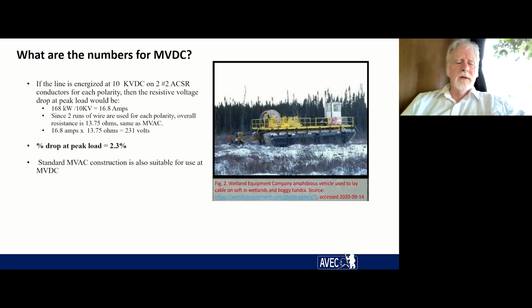This is straight Ohm's law. This is just DC current going through a resistance causing some heat that you lose. So I did that calculation at just 10 kV DC, and it's only 2.3%. So almost comparable, apples to apples, even though the approach is totally different for MVDC as for MVAC. So this is interesting. We have the opportunity to put a transmission line in and operate it in DC instead of AC. Next slide, please. Oh, and before I go, there's one of the ways to trench in a cable, which I'm going to talk about in a minute. Next slide, please.